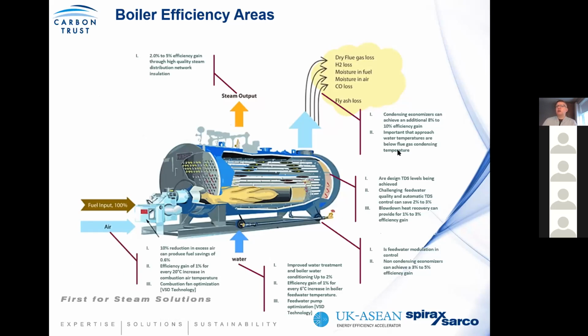It was mentioned earlier about excess oxygen and the ability to control to acceptable oxygen levels as part of the stoichiometric combustion process. However, please note that certain fuels will demand certain amounts of excess oxygen. So don't be misinformed or misled into saying, oh, for my biomass boiler, I can operate at 2.5% excess oxygen, because that's what my neighbor who has a natural gas boiler has. Different boiler types and different fuels will have different excess oxygen requirements, but a simple 10% reduction in excess oxygen within the control parameters of your boiler can get over 0.5% efficiency gain. You can also look at combustion air preheating where there's waste heat. For a simple 20 degree increase in combustion air temperature, you can get an additional 1% boiler efficiency.